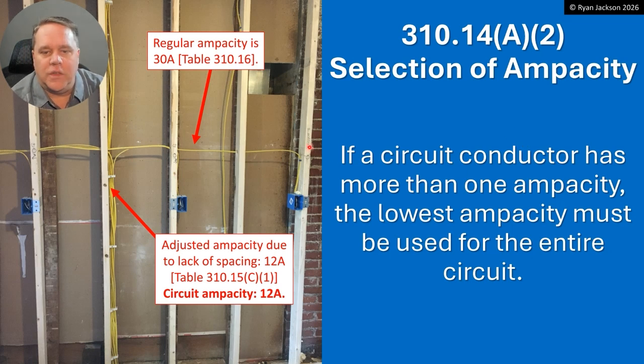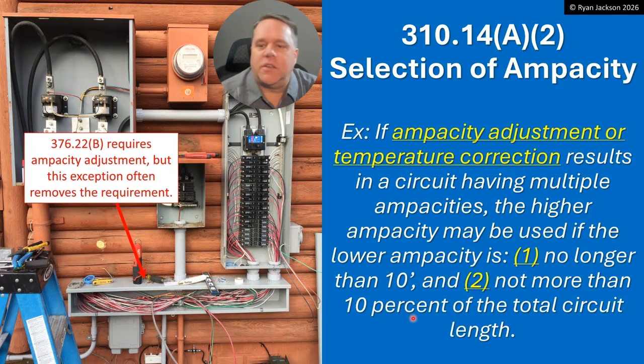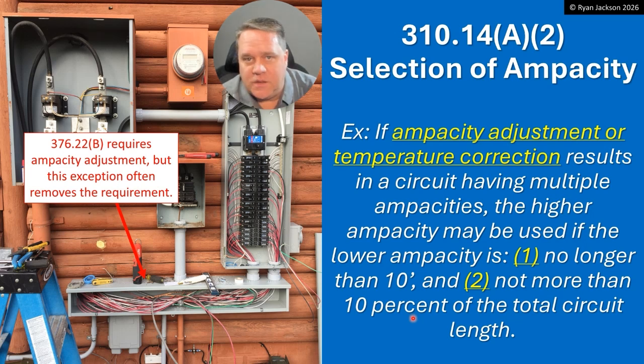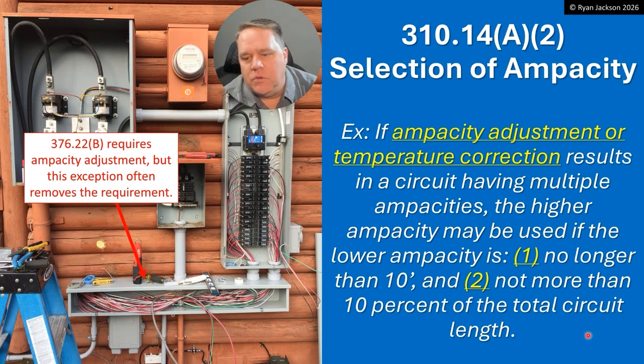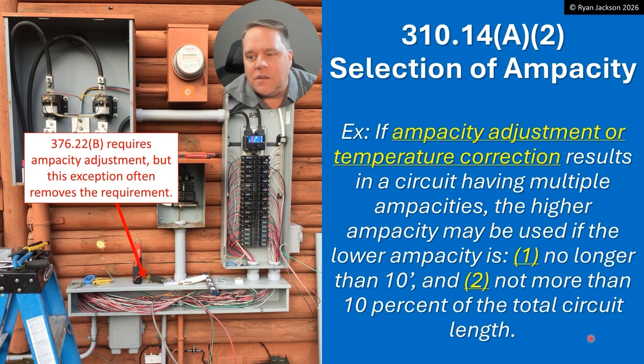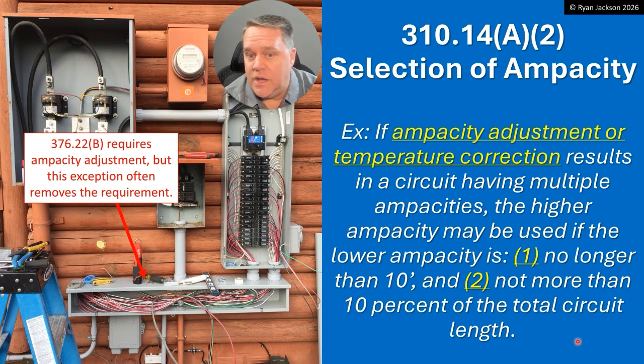The rule says you have to use the lower ampacity for the entire circuit — this entire circuit is now only a 12-amp wire. That makes sense. But there's long been an exception that a lot of people aren't aware of, and it's one you really ought to take advantage of. Without the code change text first: if a circuit has multiple ampacities, the higher ampacity can be used if the lower-ampacity portion is no longer than 10 feet and not more than 10 percent of the total circuit length.